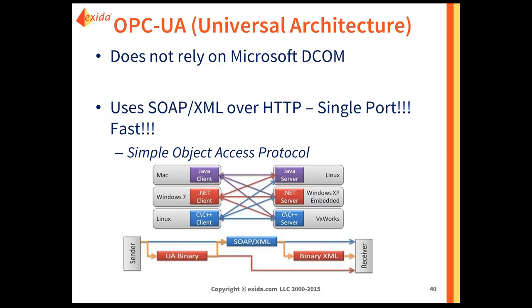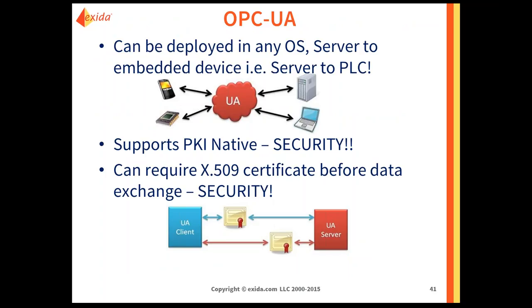That dynamic port behavior makes firewalling OPC Classic very difficult until new technologies solved it. One new technology — not yet adopted in industrial control systems — is OPC UA, or Universal Architecture. OPC UA does not rely on Microsoft's DCOM, so it can run on almost any platform, unlike OPC Classic which was dedicated to the Microsoft platform. OPC UA uses SOAP and XML over HTTP, is a single port, fast, device agnostic, and has security, encryption, and redundancy built in — a very robust and secure technology.